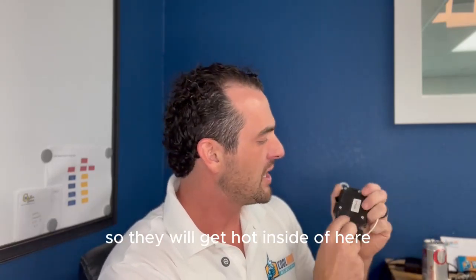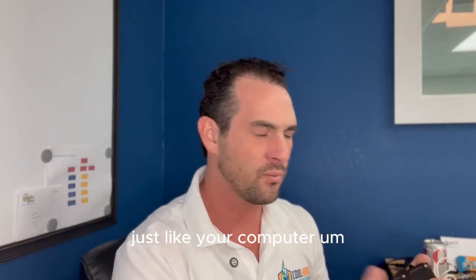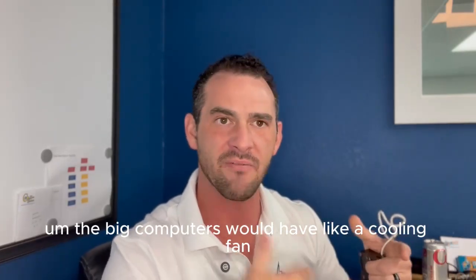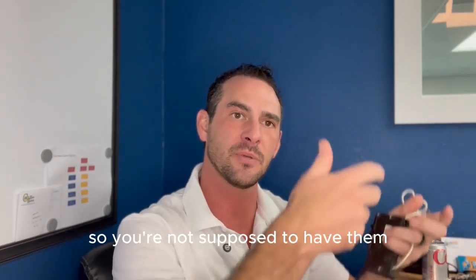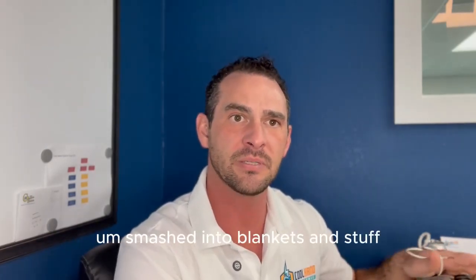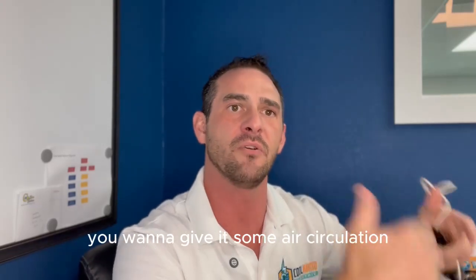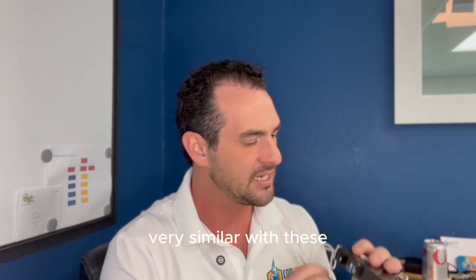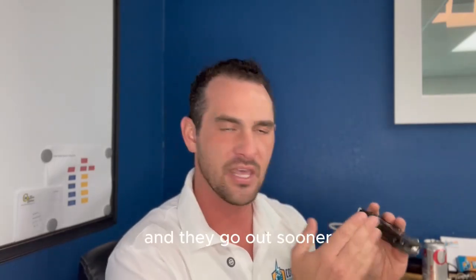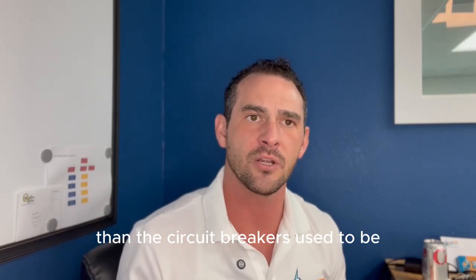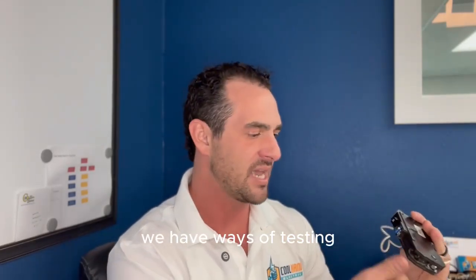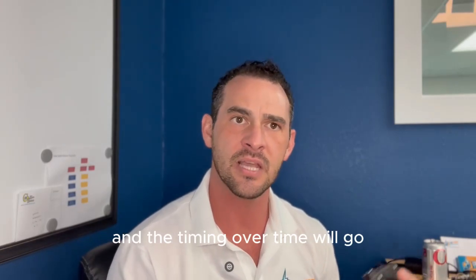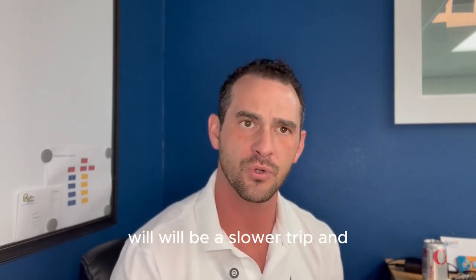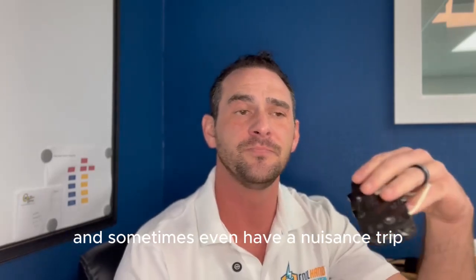So they will get hot inside of here in the electronics, just like your computer. The old school big computers would have a cooling fan. Even with your laptops, you're not supposed to have them smashed in blankets and stuff while you're working on it. You want to give it some air circulation, and that just cools off the electronics. Very similar with these. They're stacked together, they get hot, and they go out sooner than the circuit breakers used to. And when you test these, we have ways of testing how quickly it can trip, and over time the timing will be a slower trip, and sometimes it even has a nuisance trip. It'll trip on new appliances and whatnot.